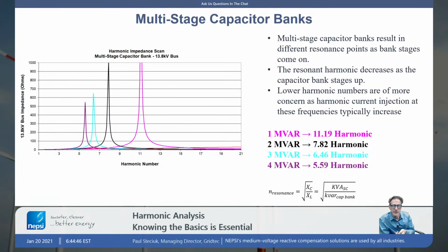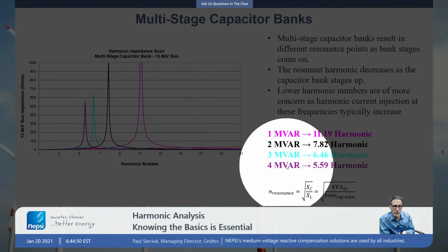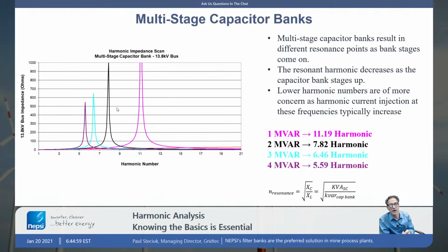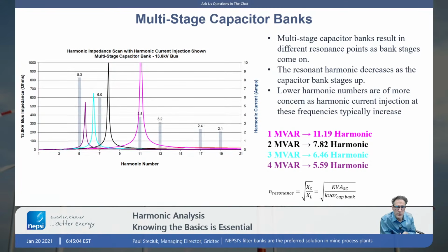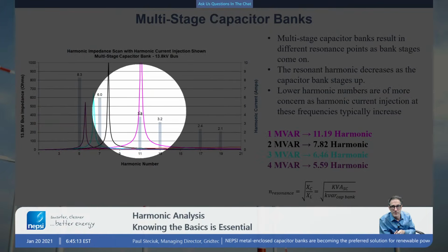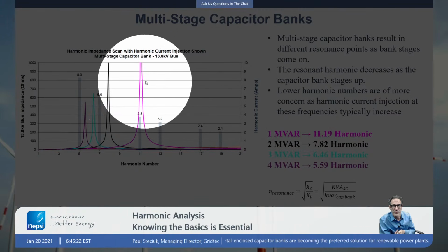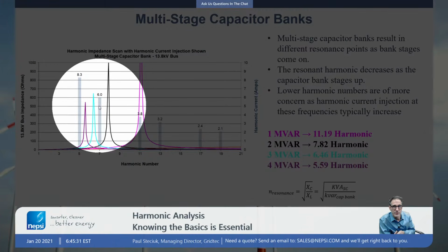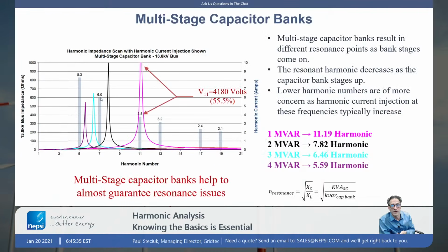Multi-stage cap banks we show here, and in this case we have 1 megavar, 2, 3, 4, the original values of capacitance that we're putting on. That results in four resonant conditions depending upon how many stages are online. So we can overlay our current injection values, and we can see that at this one here, 3.8, my 11th harmonic current injection corresponds to the resonance at the 11th when I have 1 megavar on. So 1 megavar could potentially be a problem. We've already identified this one over here, that with a slight shift in the impedance curve, I might have a problem there. You could say the same here. Slight shift in impedance, I might have a problem. But in this case, you can see that just this one alone, at the 11th, that harmonic current multiplied times the impedance, I get a value of 4,180 volts of voltage distortion, so 55%.